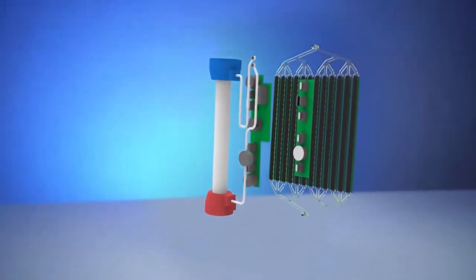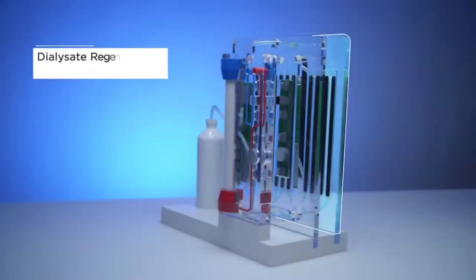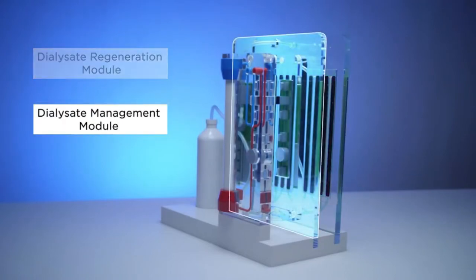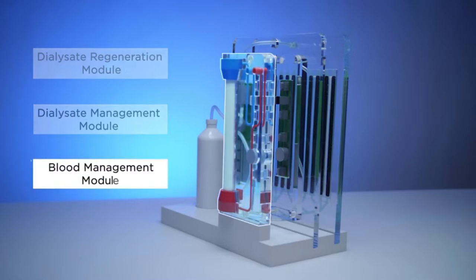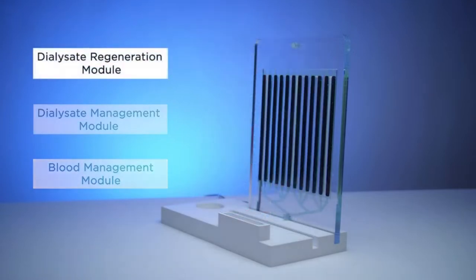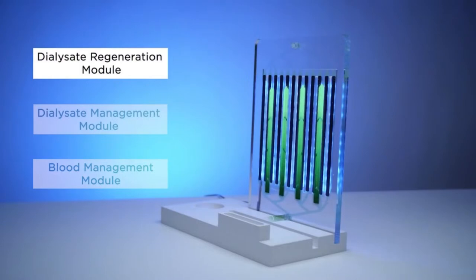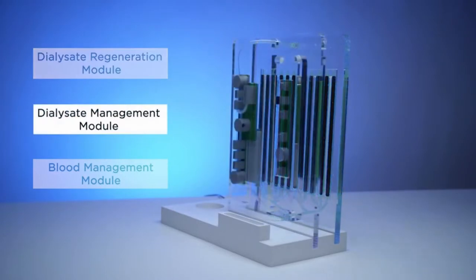The Active is comprised of three modules: the dialysate regeneration module, the dialysate management module, and the disposable blood management module. The dialysate regeneration module removes toxins from the spent dialysate. The dialysate management module directs the dialysate through the Active and contains the electronics, software, pumps, and sensors required to safely and effectively manage the dialysate and overall device operations. This module also proportions electrolytes into the regenerated dialysate stream returning to the dialyzer.